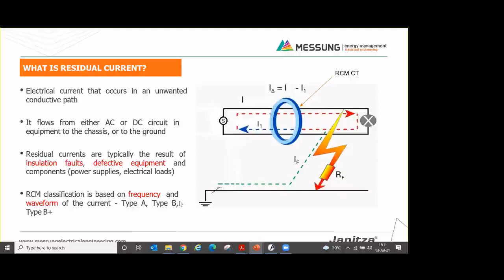Now, let's see why to use RCM, meaning why it is important to monitor residual currents. The answer is to ensure uninterrupted, that is continuous, power supply, because there are facilities such as hospitals, data centers, critical manufacturing plants, or pharmaceutical industries which require 24/7 power supply. In those cases, the choice of an RCCB, that is the residual current circuit breaker, would not be a good choice because it will trip, that is, it will shut off the supply on occurrence of a fault. And we don't want that.